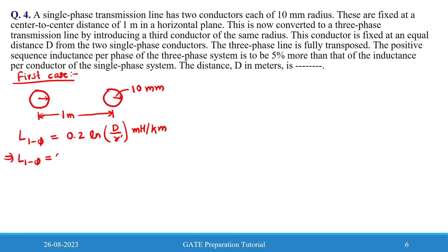L single phase will be 0.2 into ln of d, the value is 1, divided by r dash, which is 0.7788 into 0.01, millihenry per kilometer, and this will be 0.97 millihenry per kilometer.